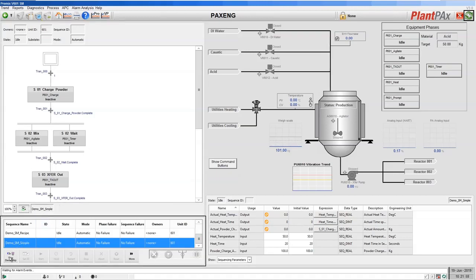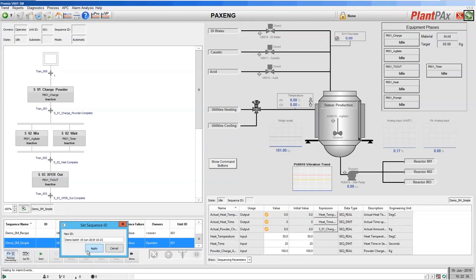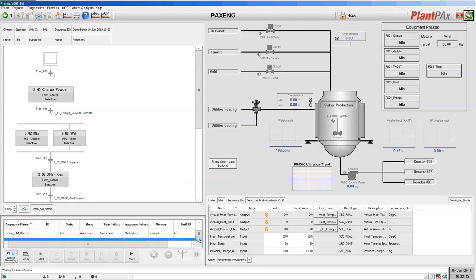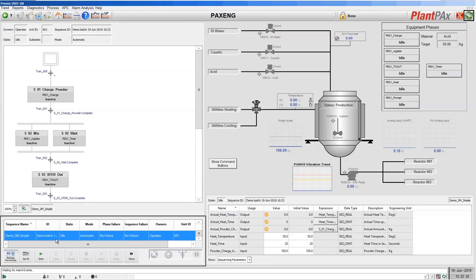Let's run a recipe. I select my recipe from the controller and need to take ownership. Sequence Manager has a concept of ownership — either an operator can own a sequence from the HMI or the controller can own the recipe from within the logic. You can set a unique ID for each execution of a recipe — your batch ID, for example. Let's give this a demo batch ID. This can be any text that you like and you can see the ID has been assigned in the controller.